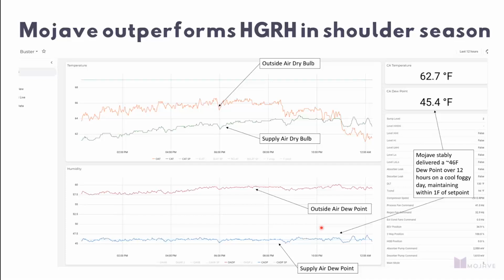An example of this is we have a unit in Michigan, and this is right out of our cellular telemetry software that we provide to clients. And this is an example of a day where it's cool and rainy, 65 ambient dry bulb, roughly over 12 hours. That's this red line here. We're doing about 2.5 degrees of cooling with a discharge or supply air of about 62 to 63 degrees. And with that ambient dew point of about 57.5 degrees, delivering a stable 45.5 degrees over 12 hours, which is a very challenging condition for traditional hot gas reheat systems to operate in and frankly maintain their dew points as well.